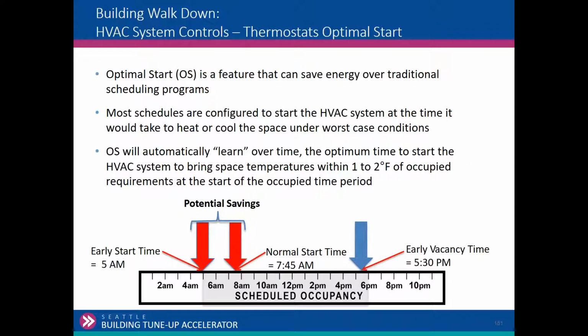Optimal start. This is a PNNL slide. For those that aren't familiar with optimal start, often called intelligent recovery, it learns, based on past demand, when to start the system. And so often what happens is we'll get a cold day like today, the operator will show up, the building's not at temperature, they'll override the schedule and start the system, hard started at 2 o'clock in the morning. Good, now I can sleep tonight because I know it's going to be warm in the morning.